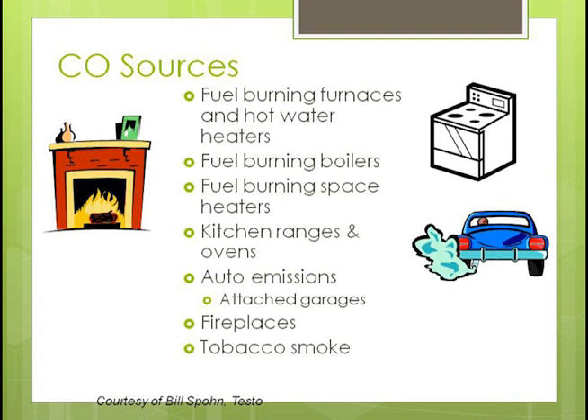Carbon monoxide sources also include kitchen ranges, auto emissions, fireplaces, and tobacco smoke. It's odorless, colorless, and tasteless, and it mixes well in the air — it doesn't stratify, meaning it doesn't settle at the bottom or move to the top of a room. It just mixes in with the air and follows the airflow.